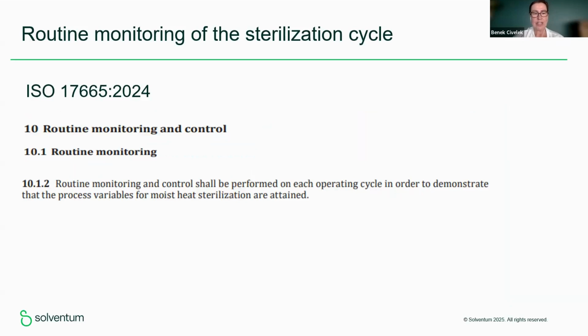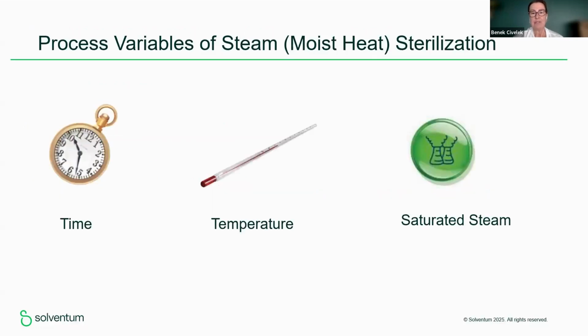In this standard, there's an important section called routine monitoring and control. Here it states that routine monitoring and control shall be performed on each operating cycle in order to demonstrate that the process variables are attained. So what are the process variables for moist heat or steam? We have three: time, temperature, and saturated steam. Saturated steam is the most important variable. And in the next slides, I will be talking about these three variables.